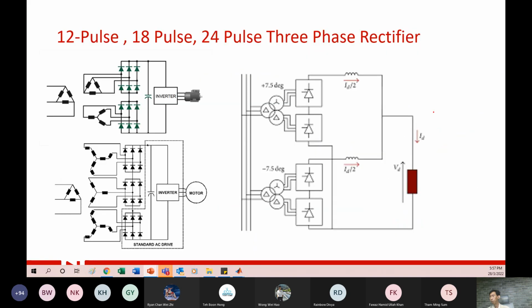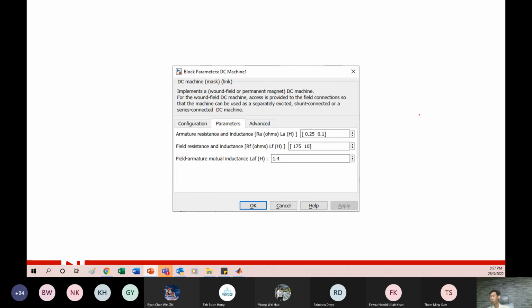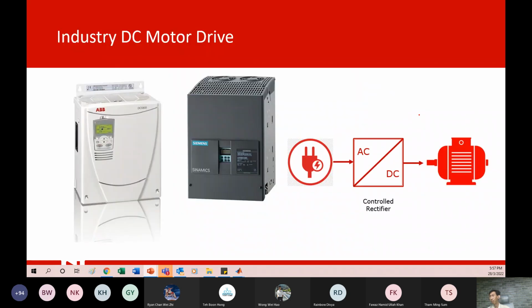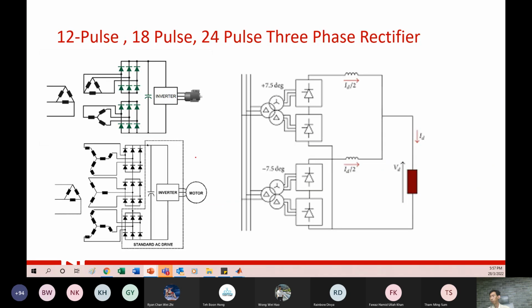All right. So far, all these rectifiers we see are what we call 6-pulse rectifiers, because there are 6 diodes or thyristors for 3-phase application. We also have 12 pulse, 18 pulse, 24 pulse, all applicable only to 3-phase. Under normal conditions, we only use the 6. But if we double up, we can connect in this way to make 12 pulse. We can triple up to make 18 pulse, and of course we can do 24 pulse.